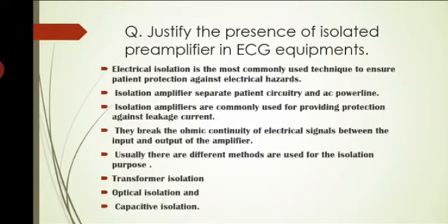Now we will see the isolated preamplifier equipment. What is the use of the isolated preamplifier? It gives isolation. Electrical isolation is the most commonly used technique to ensure patient protection against electrical hazards. Isolation amplifiers separate the patient circuitry and the AC power line. Isolation amplifiers are commonly used for providing protection against leakage current.